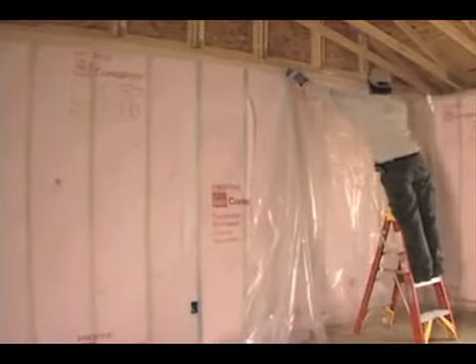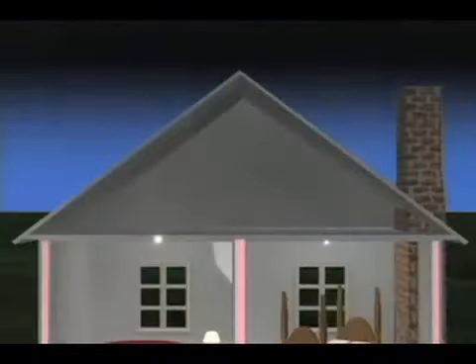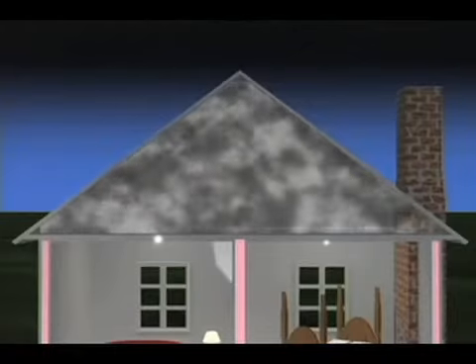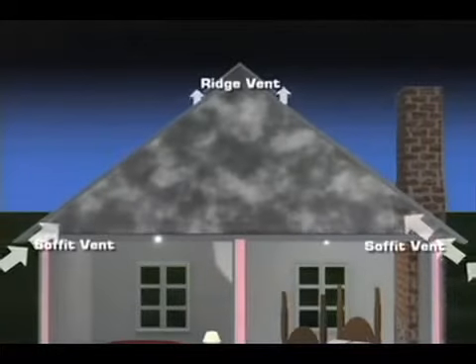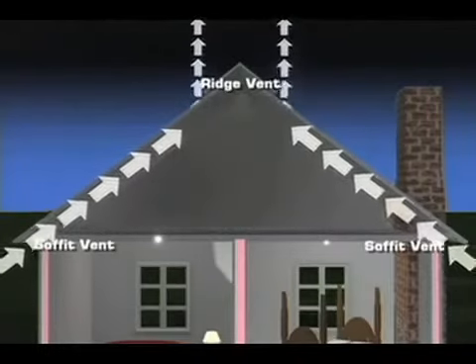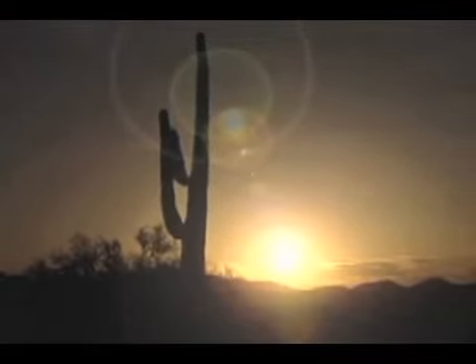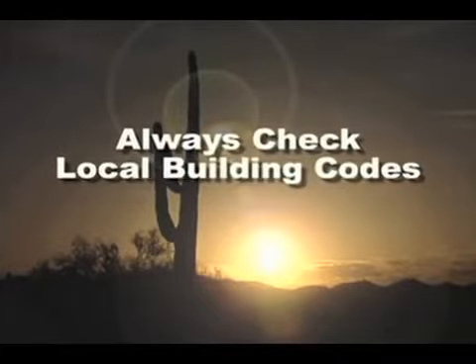and potential health concerns. This is usually controlled by the use of a water vapor retarder, a material that may either be separate from or integral with the insulation. Another technique for controlling moisture is ventilation of the unconditioned spaces that are adjacent to the conditioned areas in the building, notably attics and crawl spaces. Venting these areas draws off the water vapor that migrates through the assemblies from the living areas, reducing the chances of condensation. Note that in locations with prolonged periods of high heat and humidity, neither vapor retarders nor ventilation may be effective. Always consult your local building official for applicable code requirements.